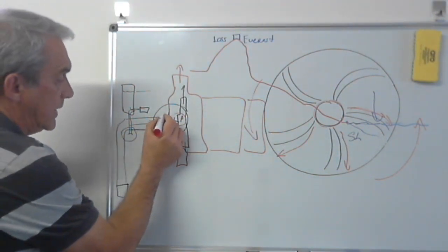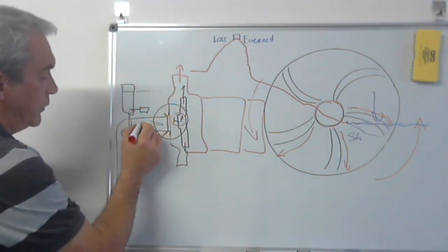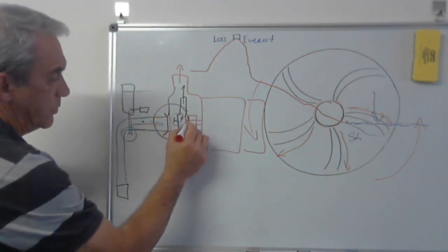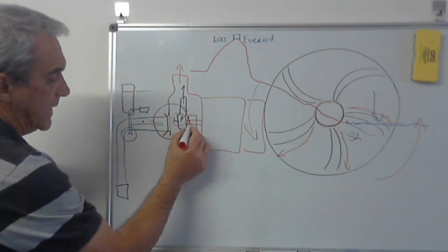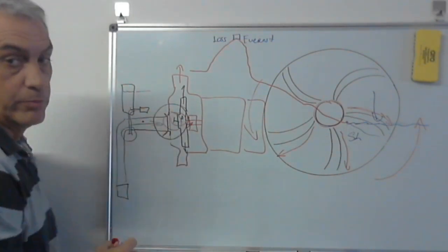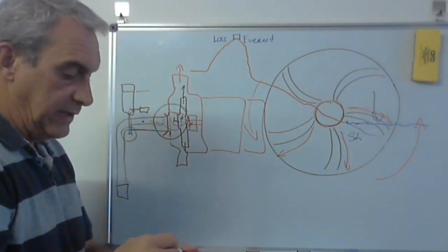If you have a leak, if you have a hole in your pipe, if you have a leaking mechanical seal, let's assume your mechanical seal is still sitting on the shaft here, and that introduces air, all these holes will collapse the vacuum. That's why when you have suction problems, 90% of pump installation failures are created on the suction.